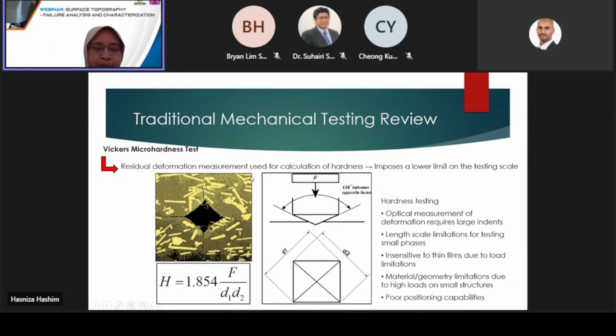As an example, this is a composite material that was tested using the Vickers micro hardness test, where the indent must be large enough to be inspected using the optical microscope. We can clearly see from these indentations that both the filler and base material were indented, or in other words, the bulk of the material was tested. So if, let's say, we want to know the hardness of the top layers, we did not achieve the intention, and we need another method, a better technique, to get a better result.